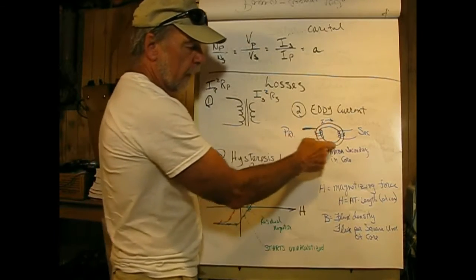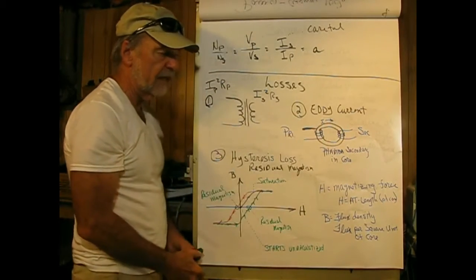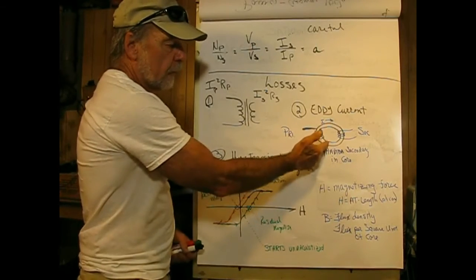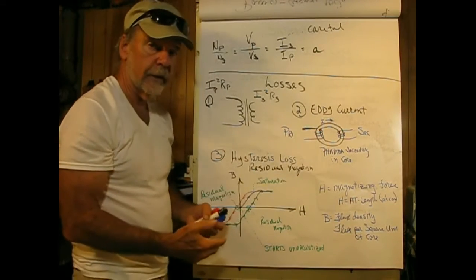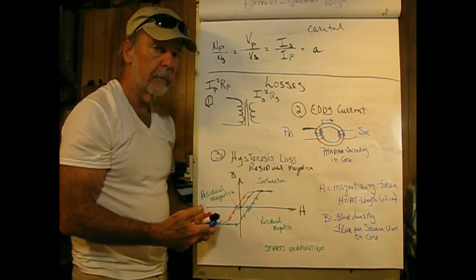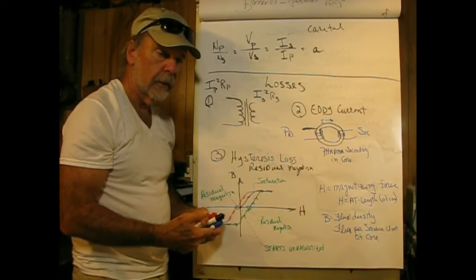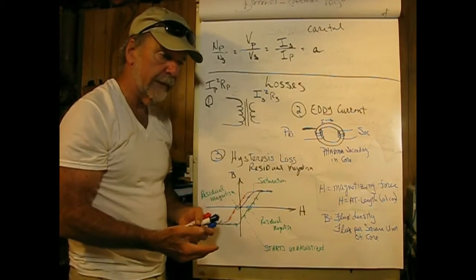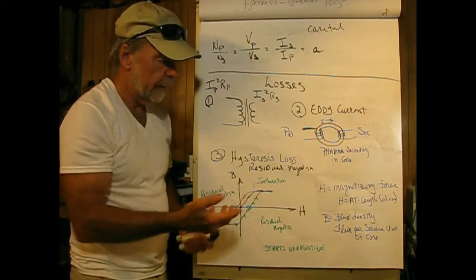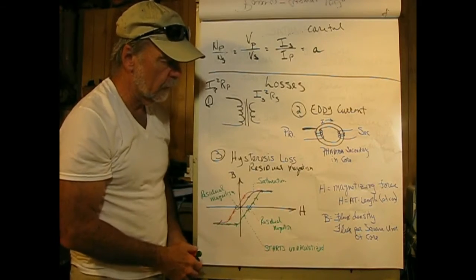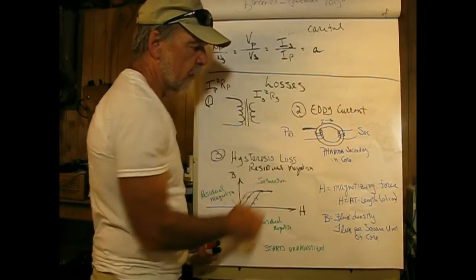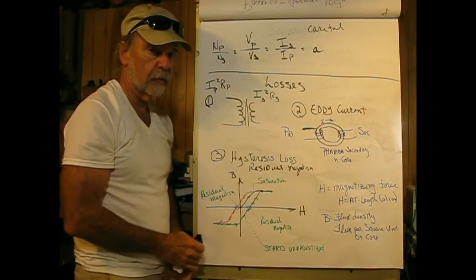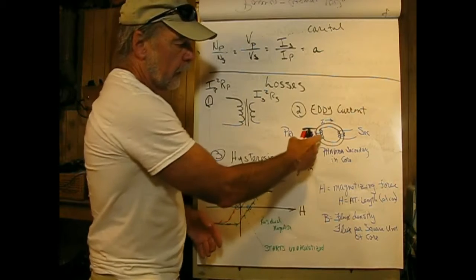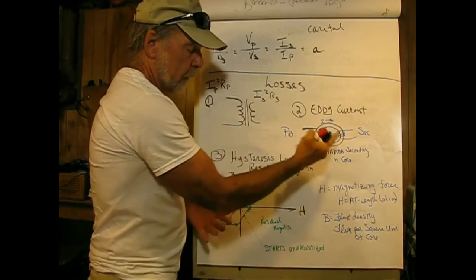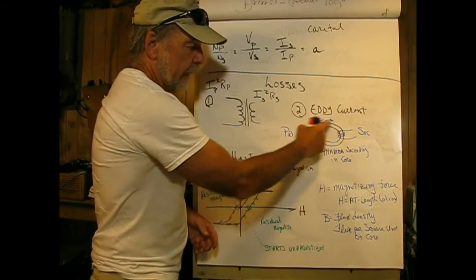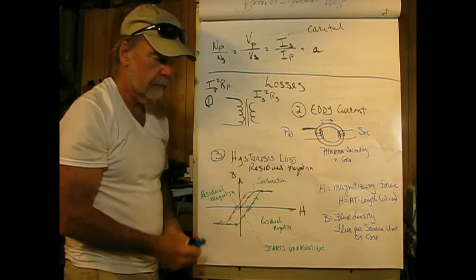Now, cores typically aren't made like this, and a lot of advancements have been made to make the core such that electricity cannot flow through it, but magnetic field can. One of the types is called an E-core, and I'd have to take one apart to actually show you what it looks like. But eddy currents have basically been severely reduced in modern transformers by eliminating an electrical path in the core itself.